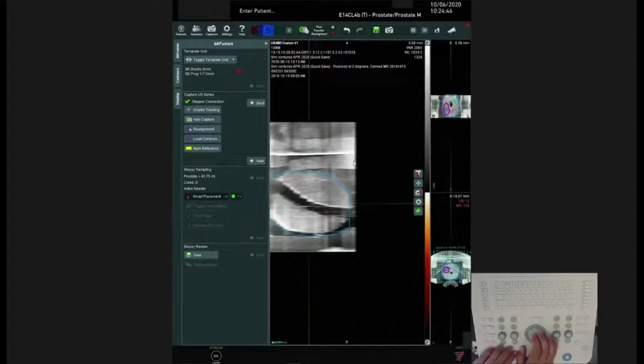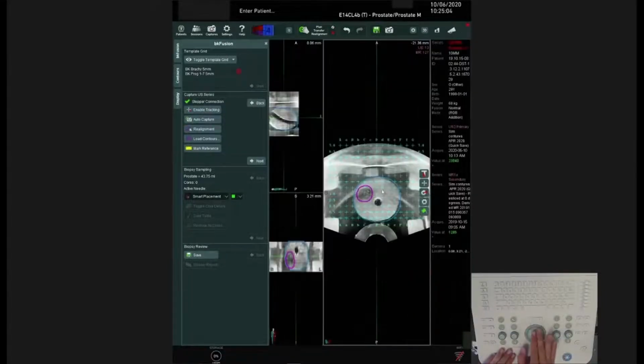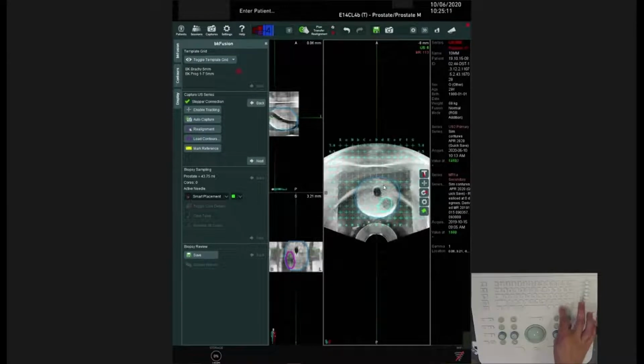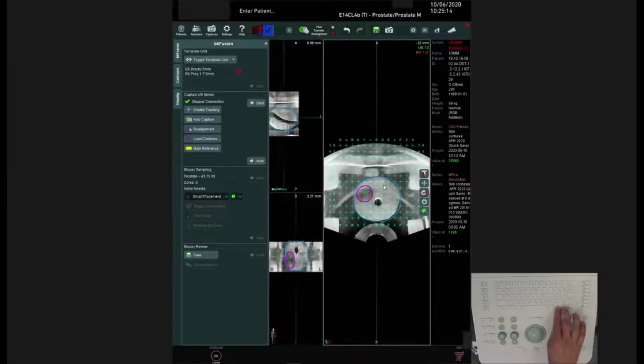Now you can adjust the contours to align with the ultrasound by moving the arrow over the Adjust Fusion tab, hold down the Select key on the keyboard, and adjust the contours by moving the trackball. When satisfied with the alignment, double-click on the sagittal image to return to the transverse image. Use the up and down arrows on the keyboard to scroll through the transverse slices to check the alignment. You can adjust the contours by clicking on the Adjust Fusion tab, holding the Select key down on the keyboard, and moving the trackball. There is also the option to rotate the contours by selecting the Rotation tab, holding down the Select key, and moving the trackball.